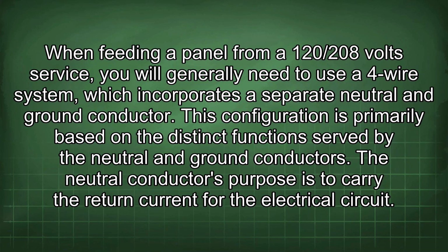When feeding a panel from a 120/208 volt service, you will generally need to use a 4-wire system, which incorporates a separate neutral and ground conductor. This configuration is primarily based on the distinct functions served by the neutral and ground conductors.